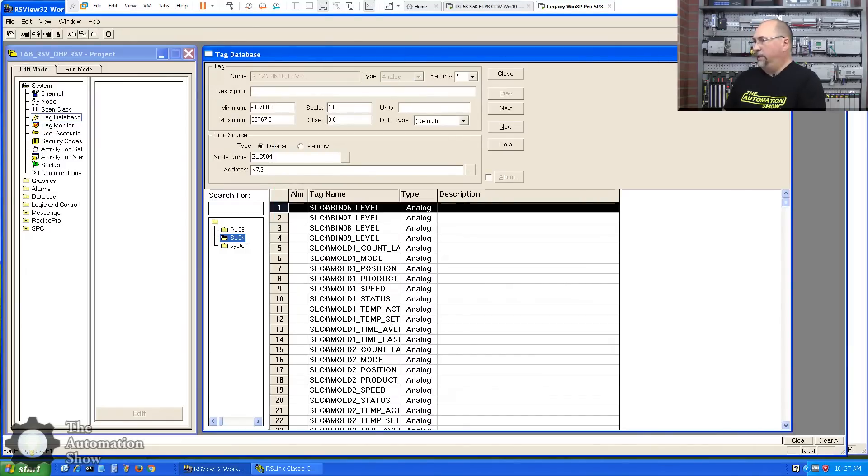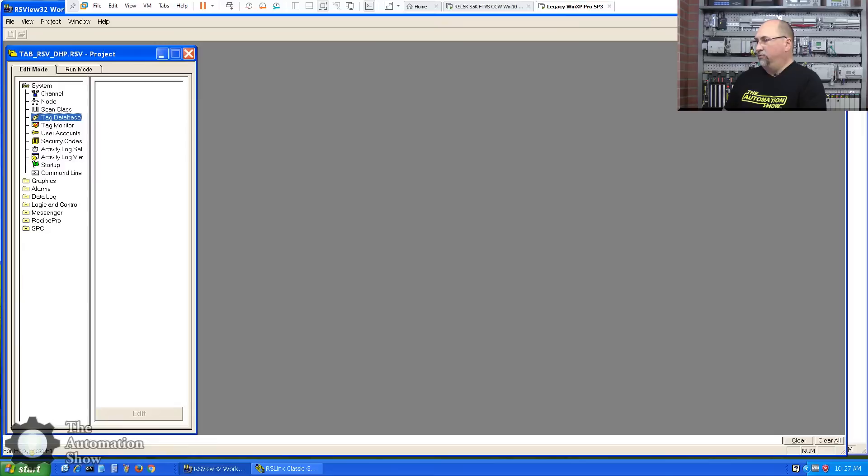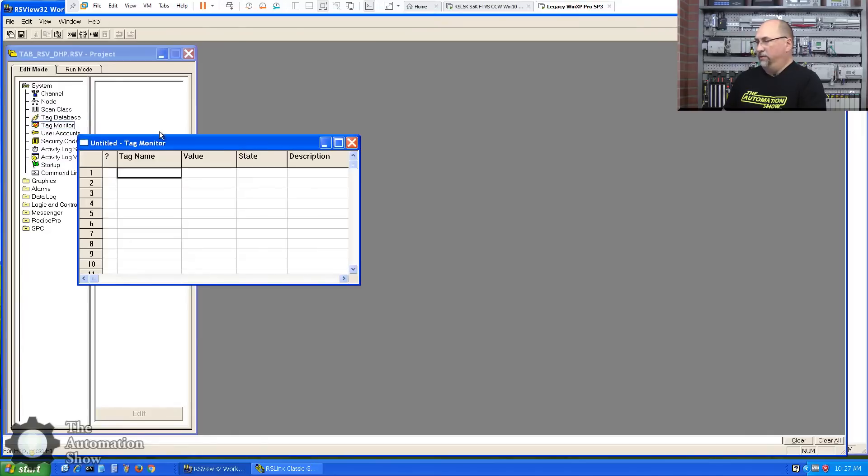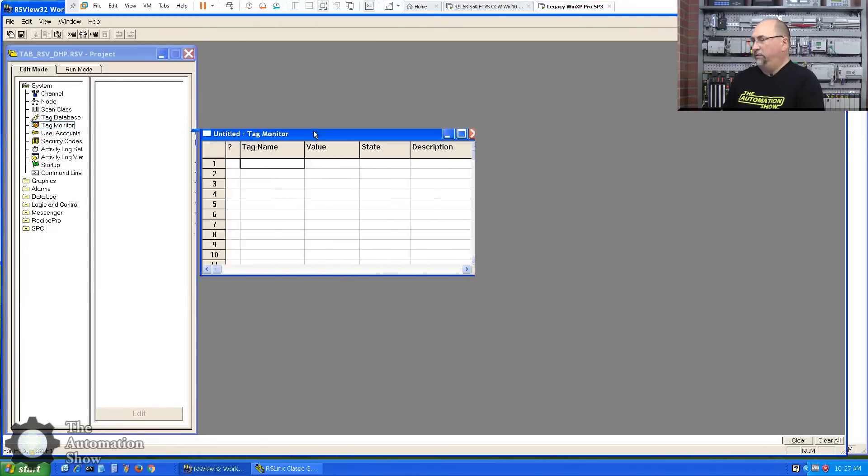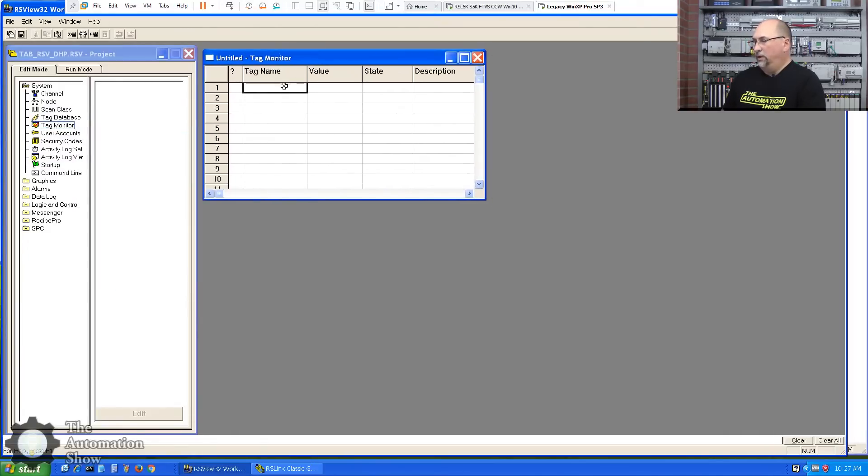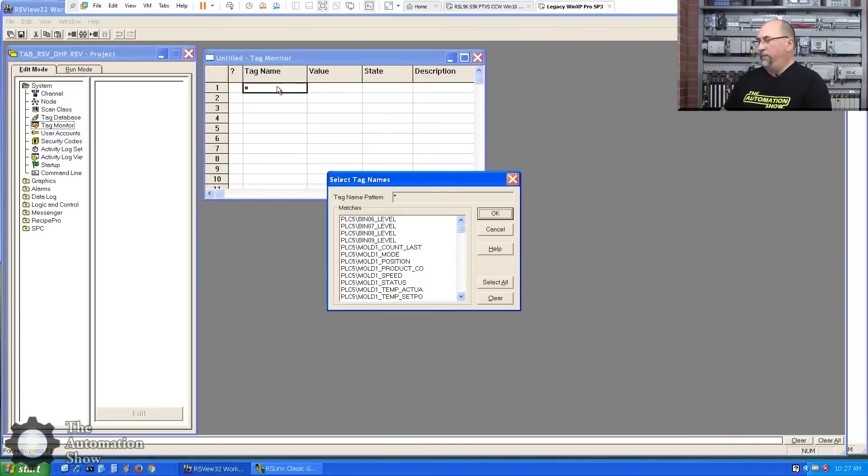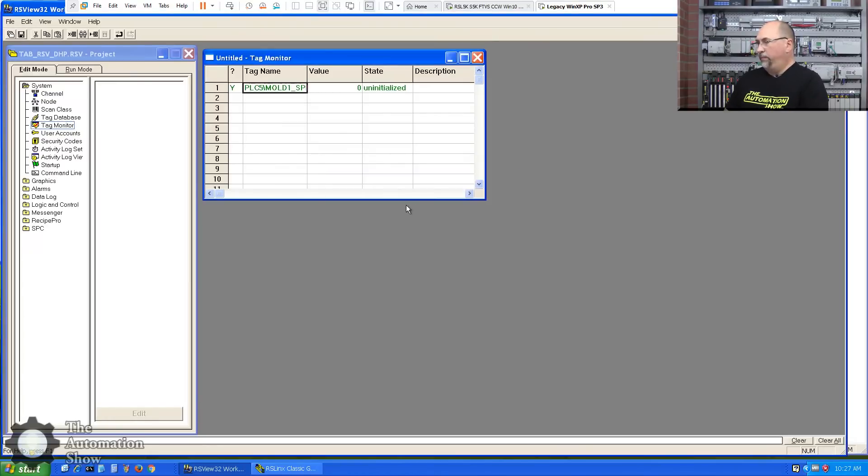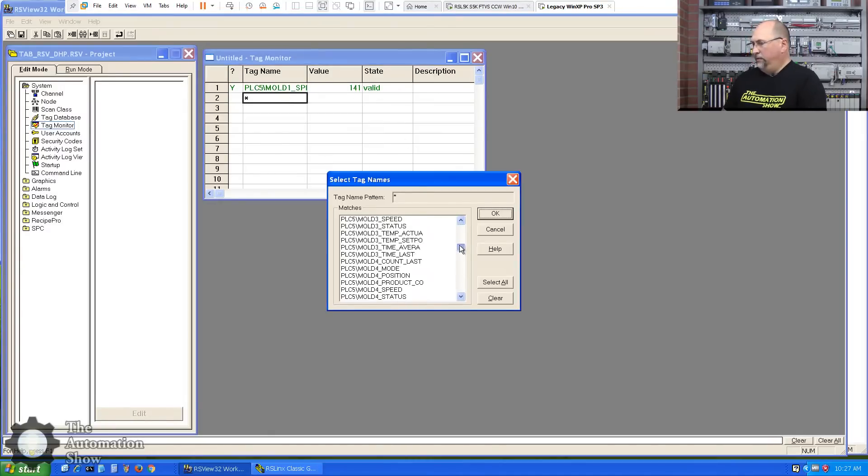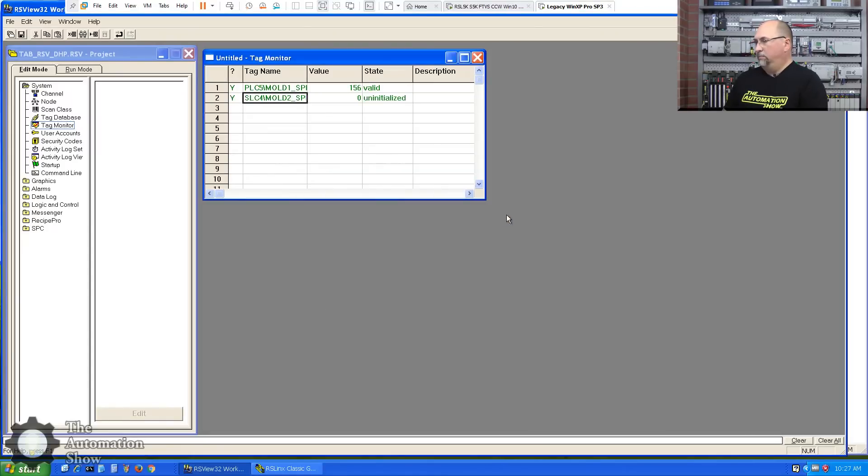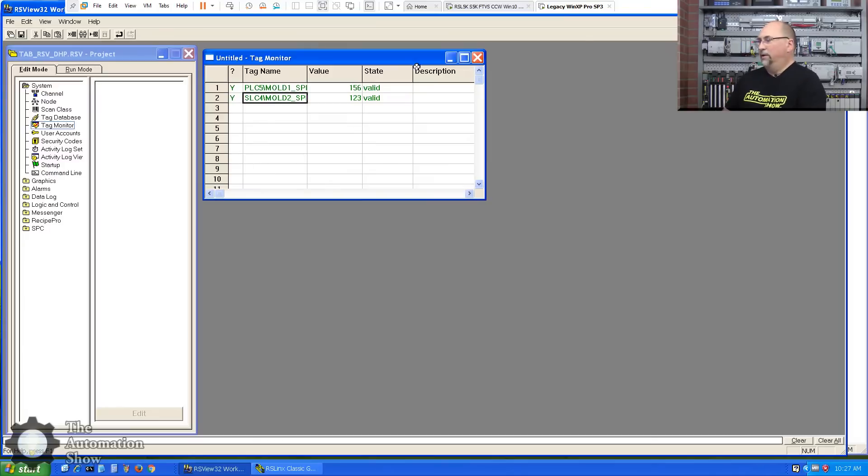So now that the tag database has been created, we'll go into the tag monitor. This is a nifty little tool. Now, a lot of people don't know this. You can put an asterisk in there and hit enter, and it will bring up your tag browser. So let's go ahead and grab PLC5 Mold 1 Speed. Okay, 141. Let's put another one in there. This time we'll look for SLC4 Mold 2 Speed. Okay, so we're getting good data. That's great.